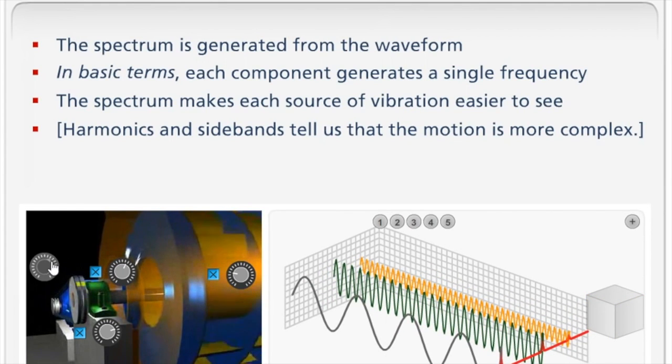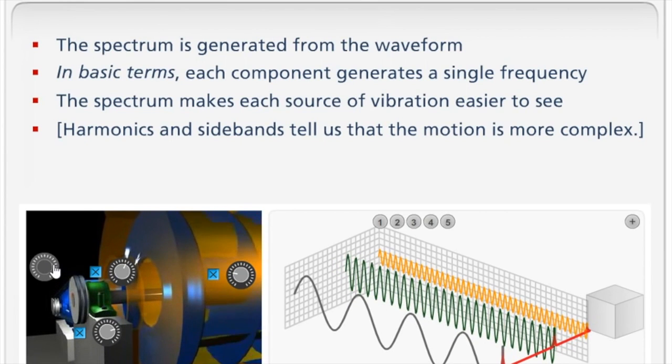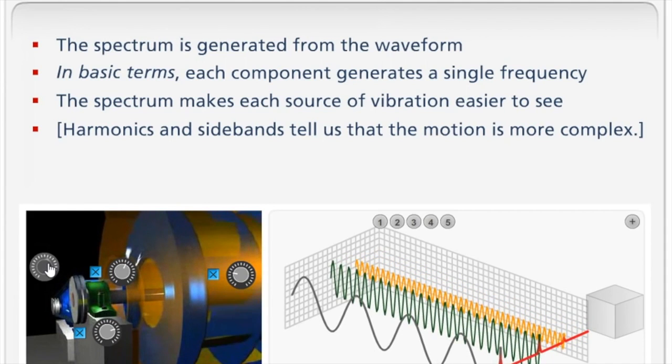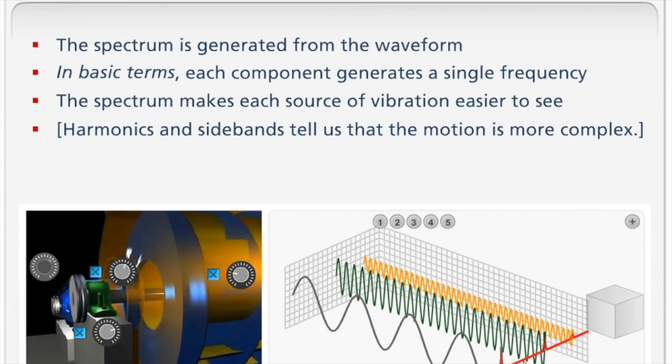If the machine is running faster the machine generates higher frequency. So you see them sort of moving off to the right. If the machine is running slower there are lower frequencies closer to the left. So this is increasing frequency and we have separated the three sources of vibration in proportion to their frequencies.